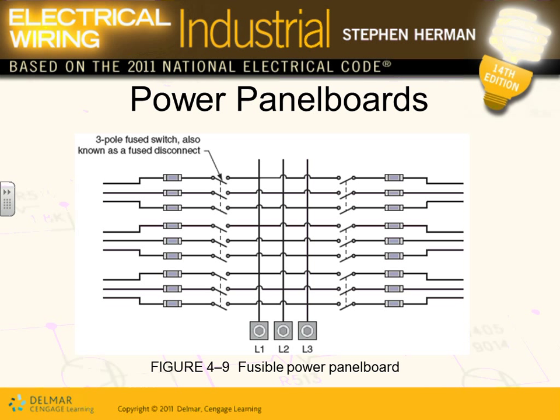When they do it this way, I don't know if anybody knows why they do it this way? Why can't they put phase A and phase A next to each other? If you did, what if you have a two-pole circuit, a two-pole load? How are you going to feed it? You can't feed a two-pole. So the way the smart people long ago discovered is they have to put the phases A, B, C, A, B, C, A, B, C, and stagger them this way, all the way through.